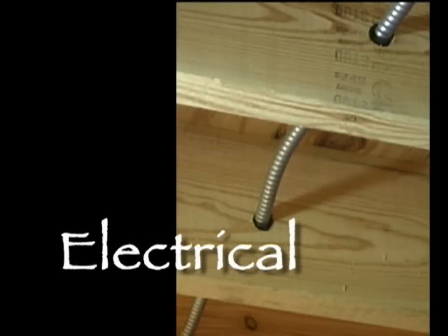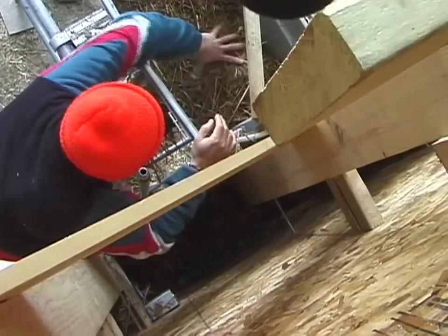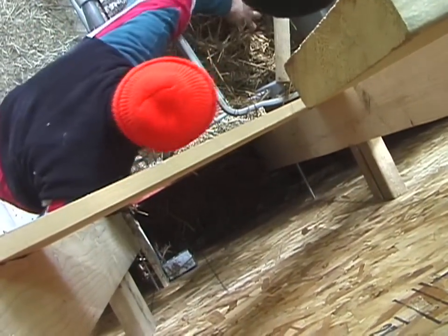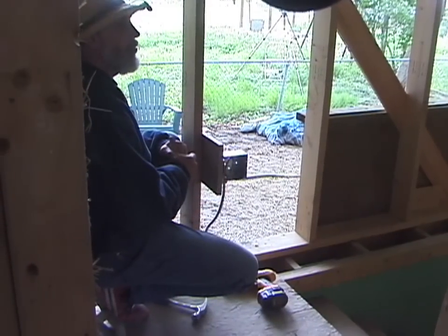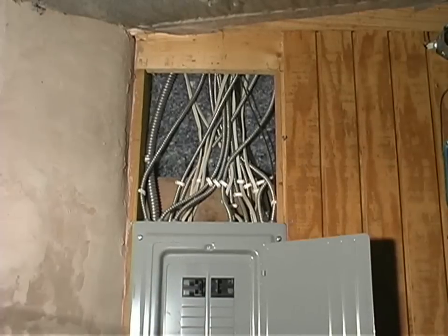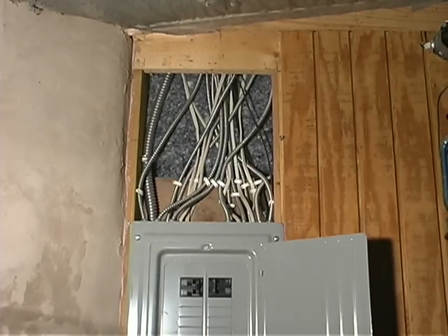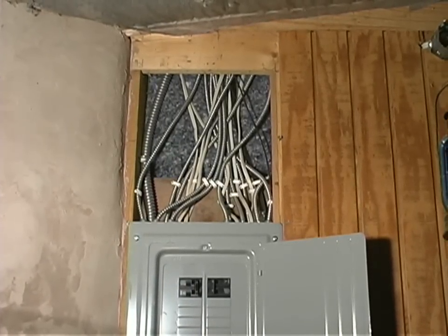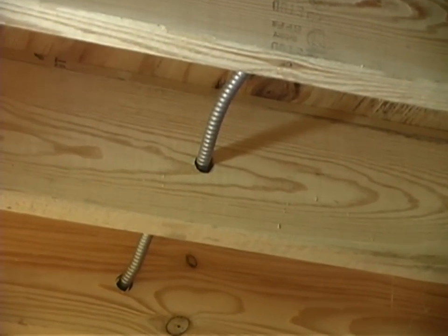In the exterior walls, the electrical wiring is conventional non-metallic sheathed type UF. It's stapled tight to the framing to avoid damage when the walls are packed with straw clay. Scrap plywood extenders bring the boxes to the interior. To help minimize exposure to stray voltage and electromagnetic fields, we use flexible MC-type wiring for circuits within 6 feet of sleeping areas.